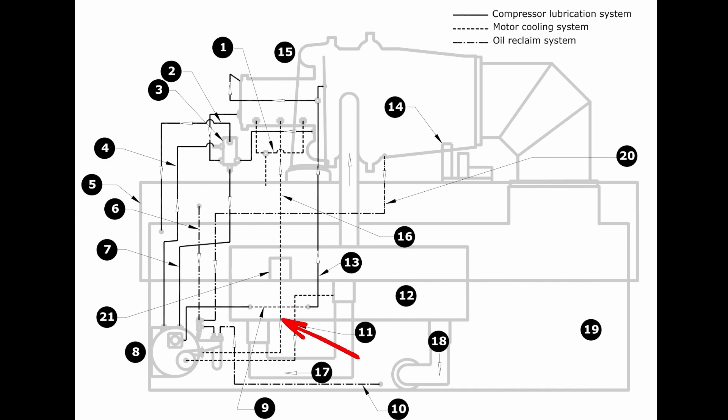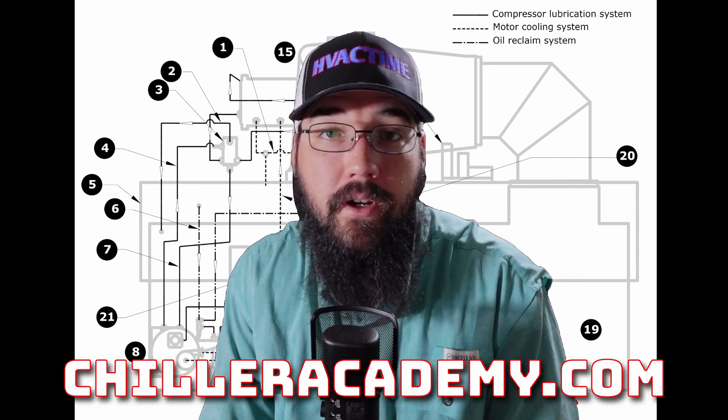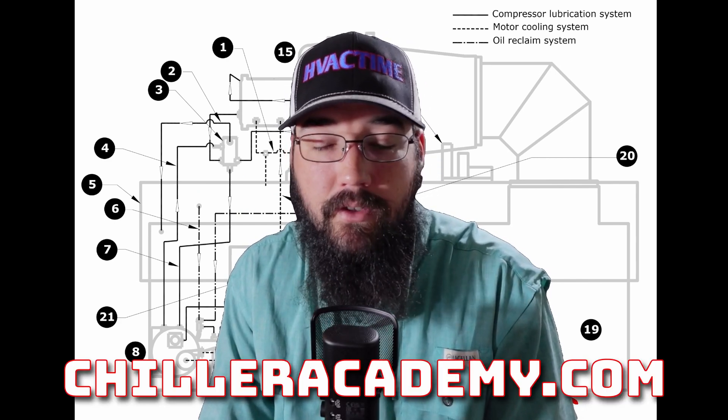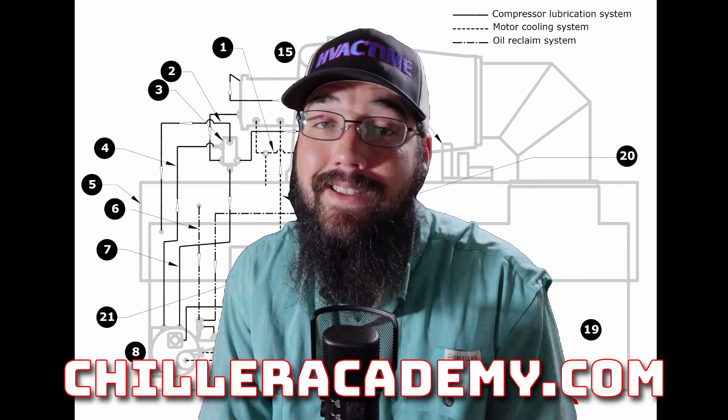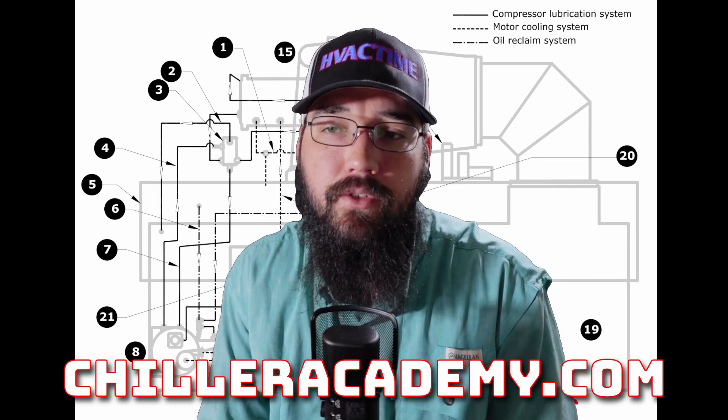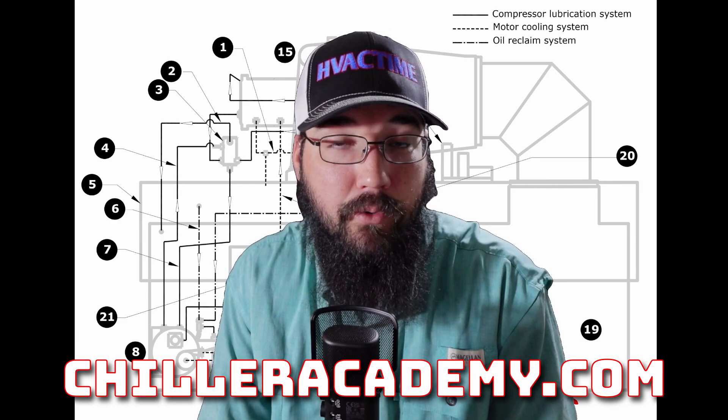That is your oil cycle for a CVH. Now it doesn't matter if it's a CVHE, CVHG, CVHF, or CDH, they're all using the same basic cycle with the same layout and components.